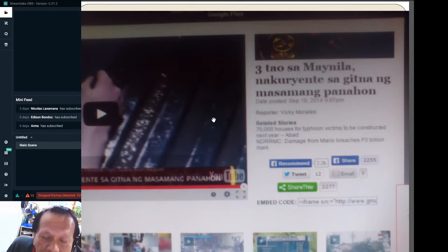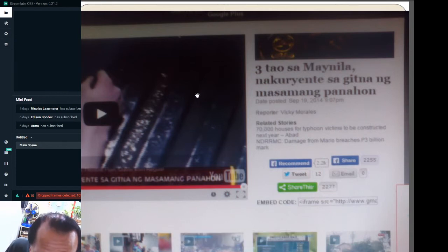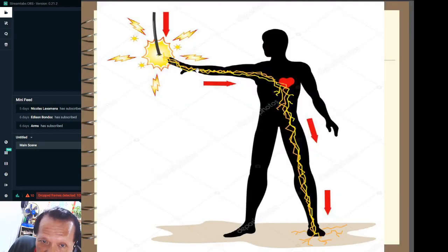I believe there's been this lacking ground fault circuit interrupter, because the moment you have a ground fault, it should be this GFCI, or ground fault circuit interrupter, or an earth leakage breaker that should isolate electricity from the non-current carrying parts, like for example the metal railings, okay, or the posts, the metal of the lighting post. Any metal which is a conductor of electricity will become a possible path of electrocution, like we mentioned earlier in this sketch, that the current would pass through our body.